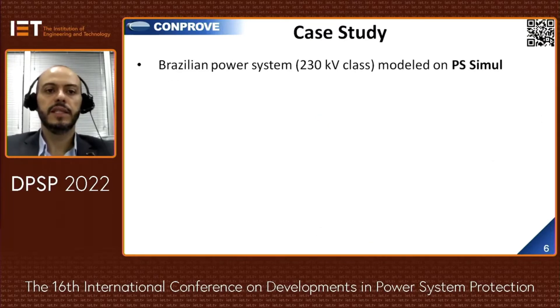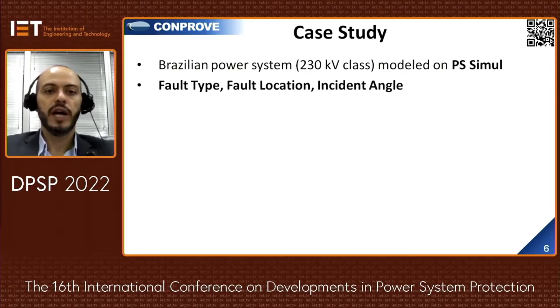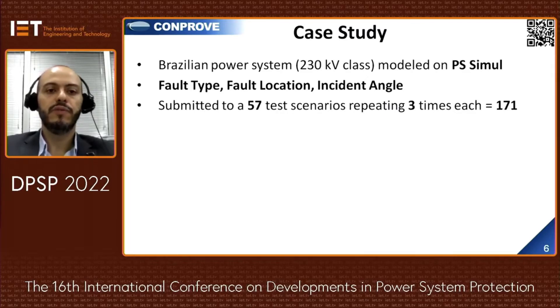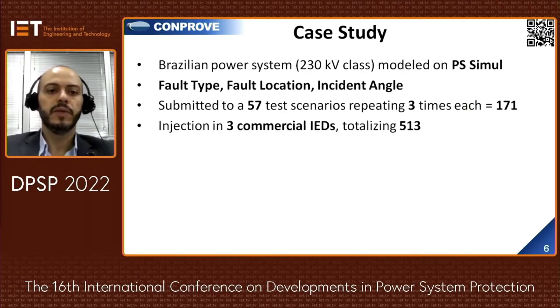The case study: a Brazilian power system at 230 kV was modeled in the software, varying fault type, fault location, and incident angle. Fifty-seven test scenarios were defined, each repeated three times, adding up to 171 tests. The same tests were performed on three commercial IEDs, totaling 513 tests.